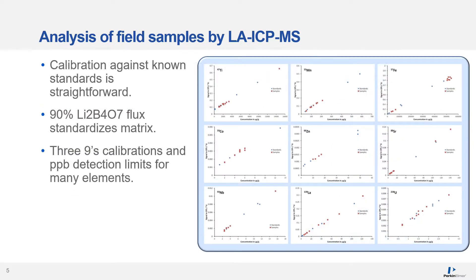This slide demonstrates the calibration of a laser ablation ICP-MS system, indicating little sacrifice to accuracy and precision. The lithium borate matrix is used to standardize the matrix response and provides three-nines correlation coefficients, as well as obtaining part-per-billion level detection limits.